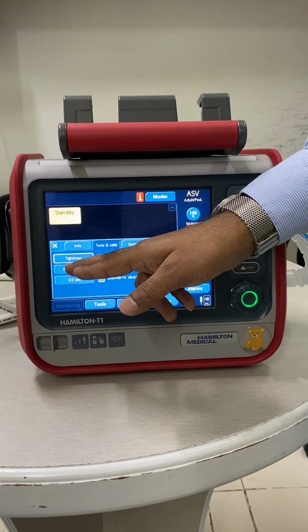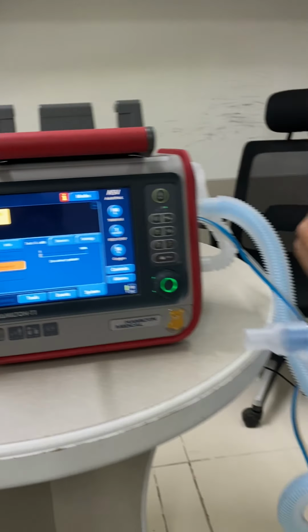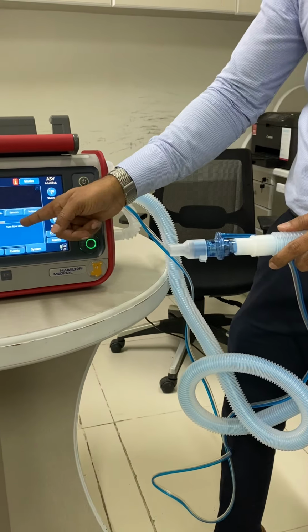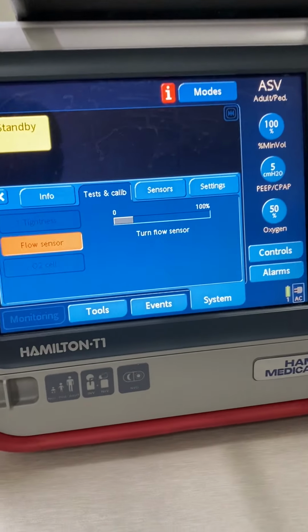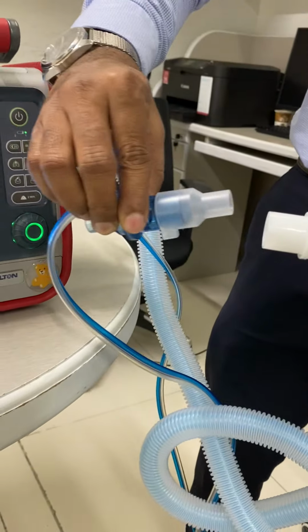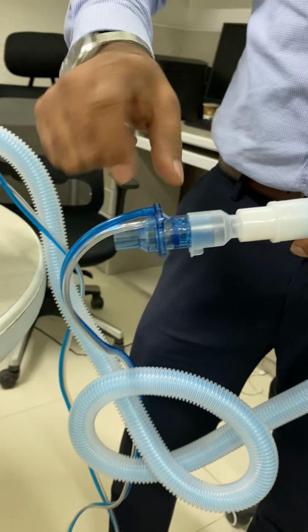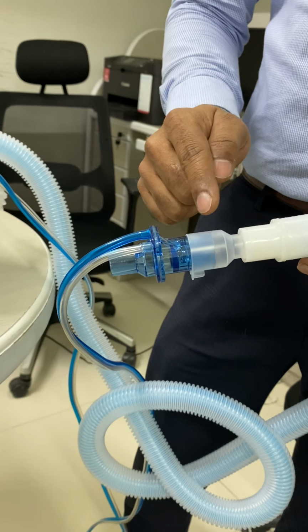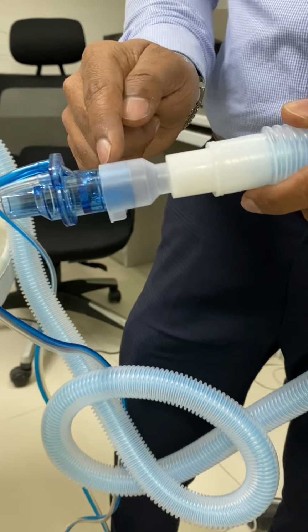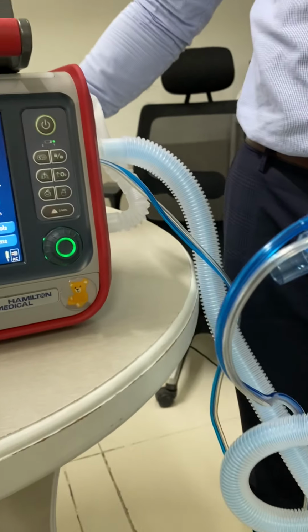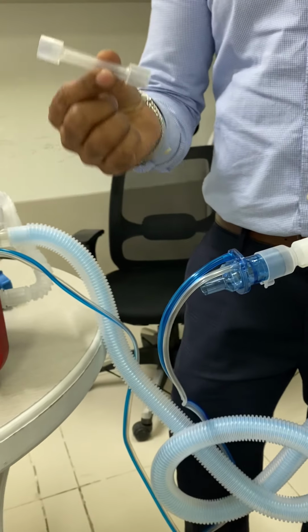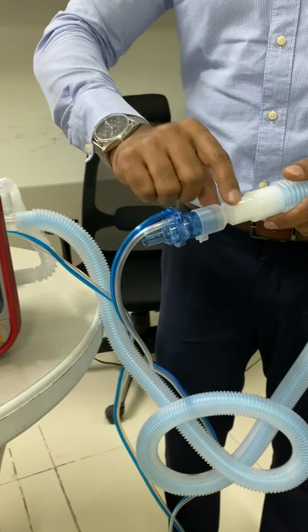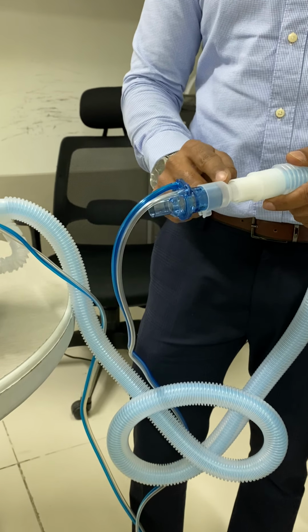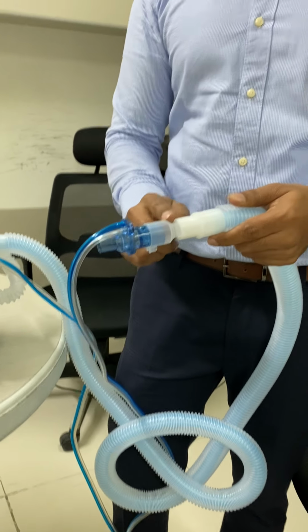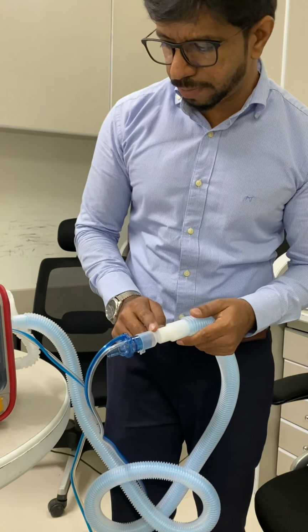Then again, for the flow sensor, press the flow sensor, disconnect the patient, and it will ask you to turn the flow sensor. So you have to remove it from the Y and connect it the other way. We have a double line tubing for the flow sensor, which is measuring the difference in both. So this adapter, which comes with every flow sensor, for the neonatal we have a smaller adapter. This adapter will help you to turn and connect it the other way. This is not a part of the patient system. This is only used for the calibration purpose.